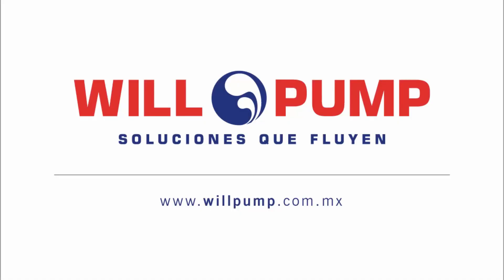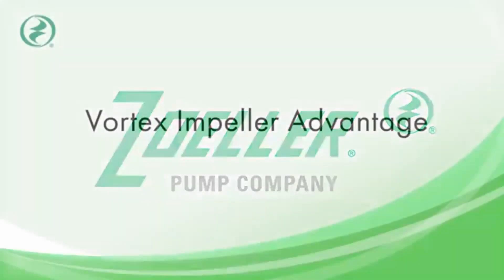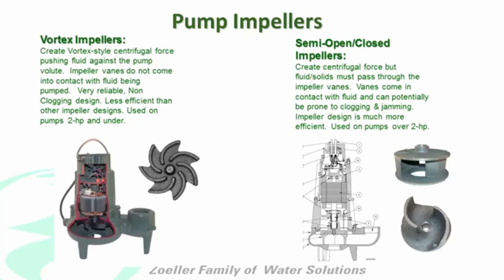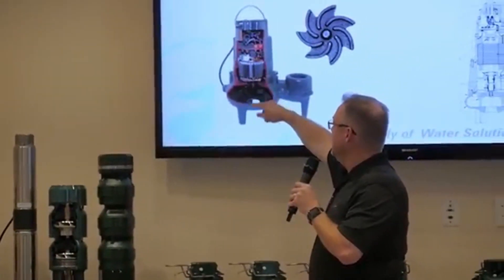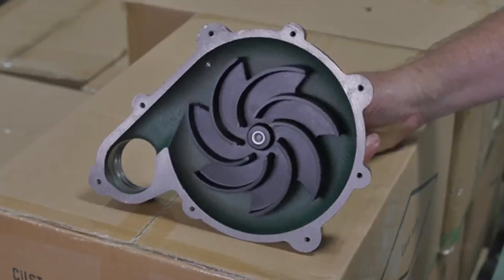Will Pump, soluciones que fluyen. Non-clogging vortex impeller design. What I want you guys to see from this slide here is that a vortex impeller sits up very high in the pump volute, and its ability to pass a solid is dependent on the distance between the bottom of that pump volute and the top of that impeller.